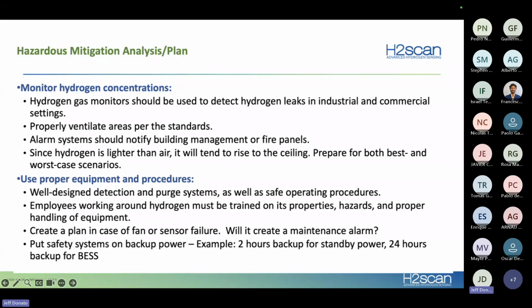And so we have to keep an eye on concentrations. I also had a site in New York City. It was a valve regulated site. They were the typical 12-volt valve regulated batteries, and they had 3 rows of batteries in 3 aisles, basically in this UPS data center room. And the outside aisles were cool, but the inside aisle was very warm. And there was a hydrogen detector above the middle aisle, and the customer said the hydrogen sensor kept going off because of basically hydrogen accumulating on the ceiling, and it was due to the temperature they were operating at.